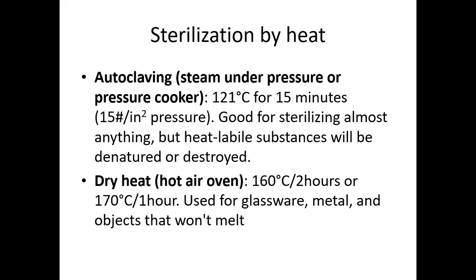Also, dry heat, hot air oven. It is sterilization by heat at 160 degrees for 2 hours, and usually this method can be applied for glassware, metal, and objects that won't melt.